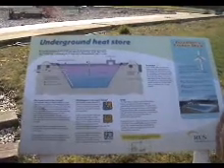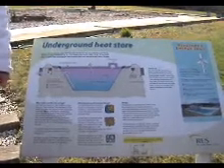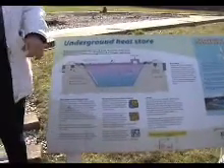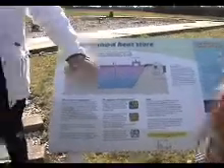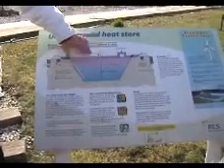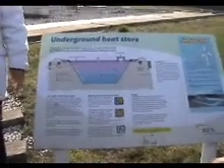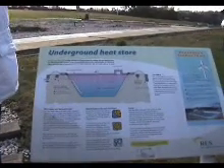It's not a very good realisation here — we knew we were going to pay a penalty for this. We've got this long distance between the point of storage and the point of use. So it's a sort of triangular circuit, if you like, which is not ideal. But nonetheless, it allows us to try the concepts and see how well it can work. And we reckon we're getting something like a 50% efficiency, which to me is surprisingly good given what we're up against, of the heat generated in the collectors and then the heat actually used gainfully in the building.